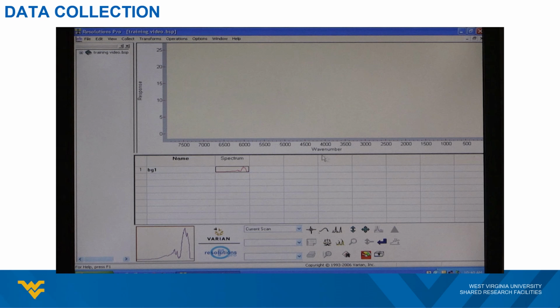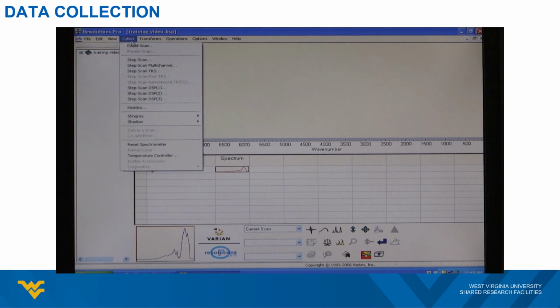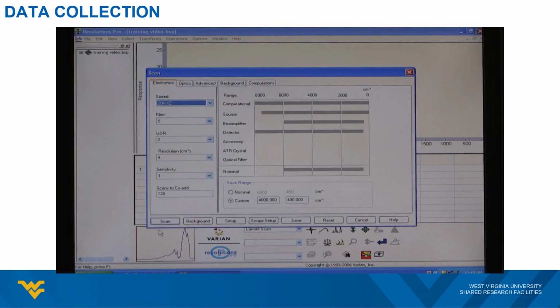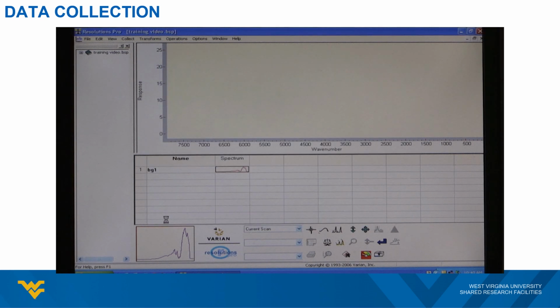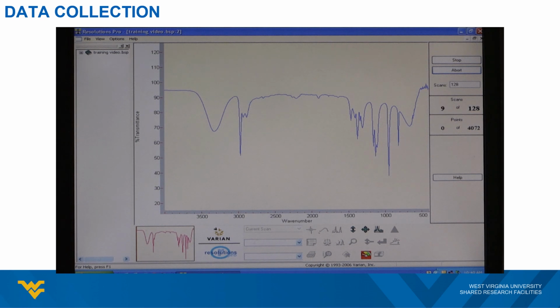Once the samples are in place, navigate to the Collect tab and then the Rapid Scan tab and click on it. This will bring us back to the Scan Setup window. Locate the Scan button and click on it to start the measurement using the parameters previously selected. The resulting spectrum will be displayed in the measurement window. In this scan, we will collect the sample spectrum 128 times as well to match the data quality of the previous background measurement. And the progress of the measurement is indicated by the numbers on the right.